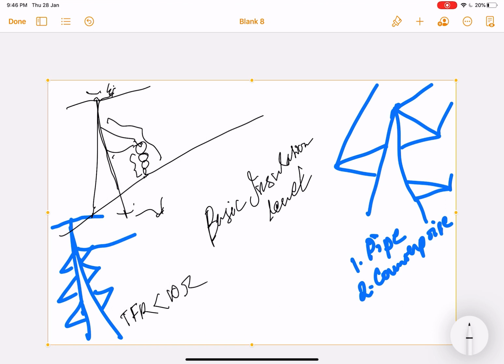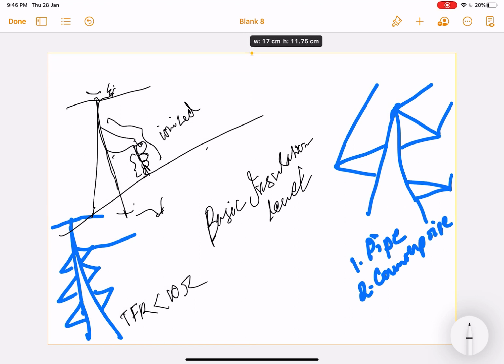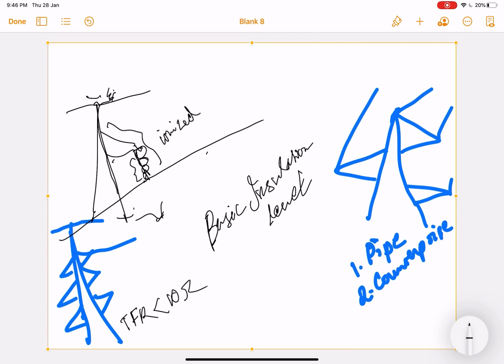So what will happen is that this path will get ionized, which is a very dangerous condition. Normally, whatever fault is there in the line or anywhere else should get dissipated to earth. But now, because this insulator has already become ionized, it will behave like a conductor, and the tower is already at such high potential. So now, from the tower, current will start flowing to the conductor. This is also known as back flashover.